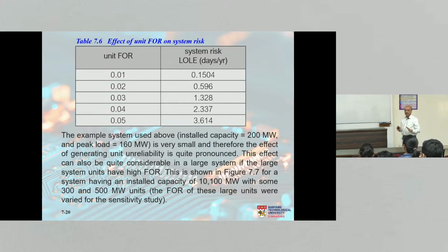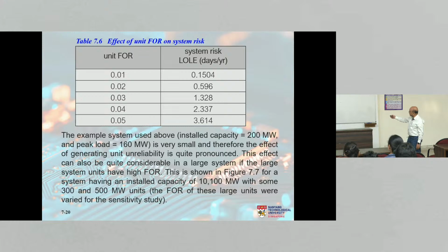We are still on generation, remember. We have assumed the transmission and distribution to be fully reliable and capable of transporting the generated energy to the load points, to the consumers, correct? I also show you a very large system result, which of course you can only simulate using a computer. So this system has a capacity of 10,100 megawatt. What's the capacity of the system that we studied here? 200 megawatt, right? 10,100 megawatt, right? This is a large system, fairly large system, and it has some 300 and 500 megawatt units.